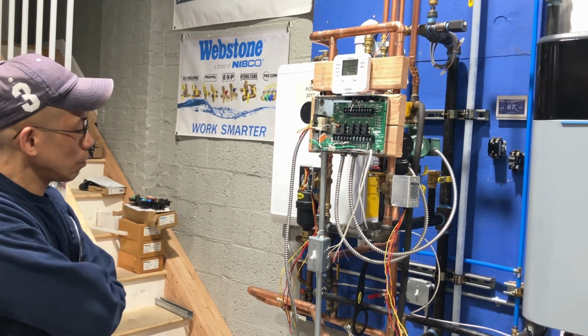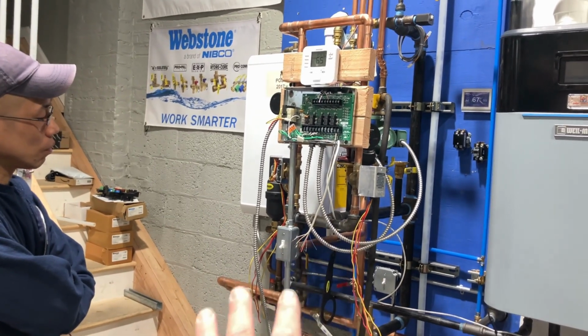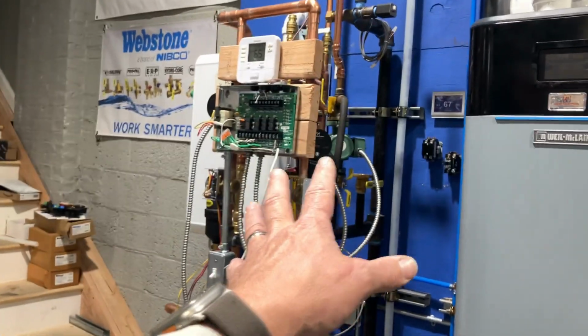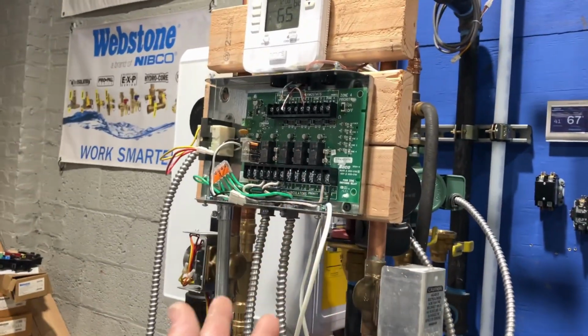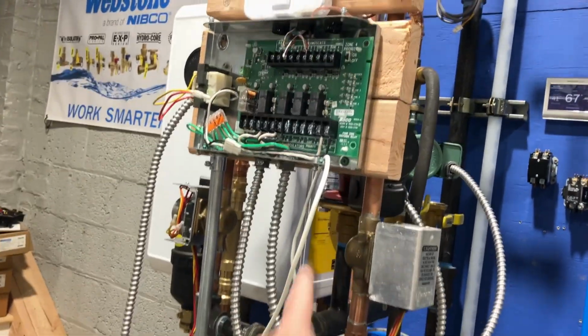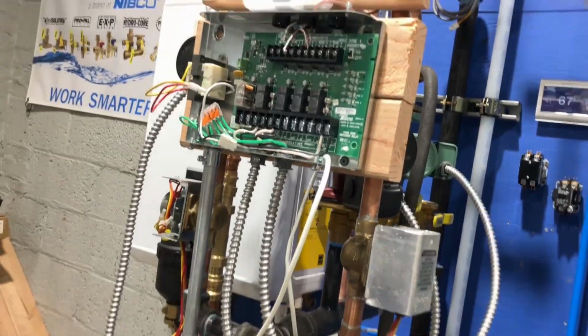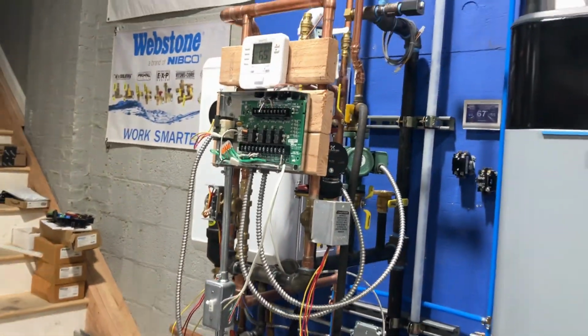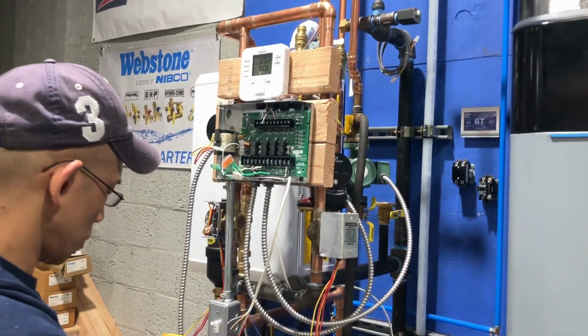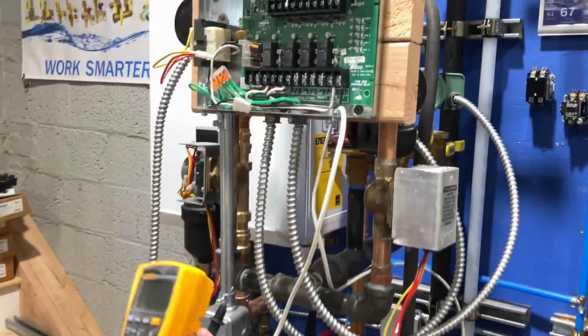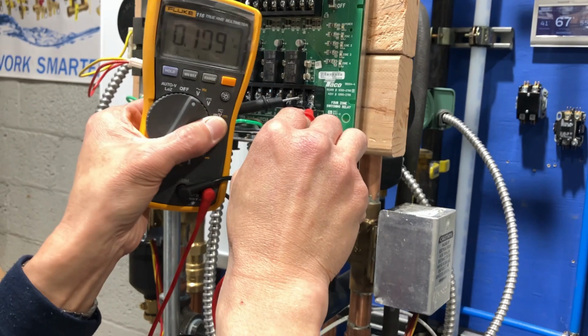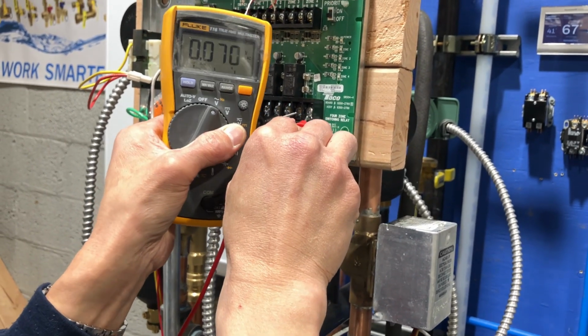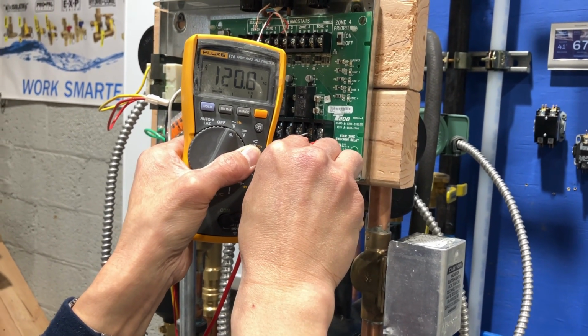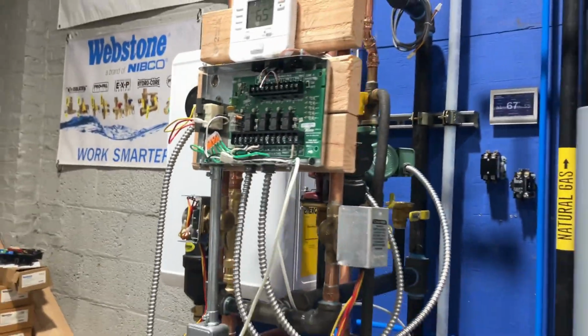Do your troubleshooting steps. Don't just turn on that switch because you think it's off. You're going to go to the system. You're going to see that, hey, I have no power. You're going to verify there's no power, which you just did. There's no power. If I turn this back on, now check. Now you have 120 volts. Yeah. So now you have power.